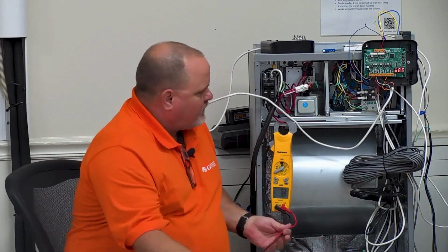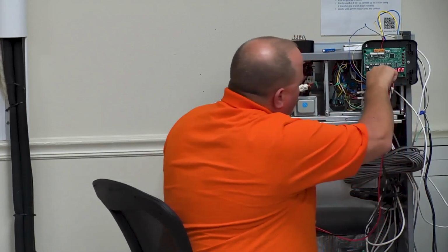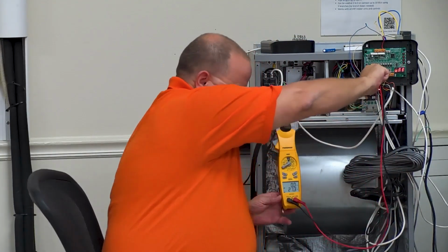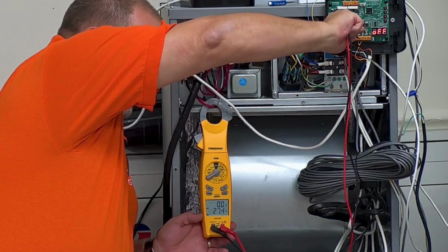So I got the voltmeter going on here. Let me get on O and C. And I got 27 volts. Hopefully my arm's not in the way. A lot of guys get confused by that. What I mean by that is your reversing valve call does not cycle with each call for operation. Your reversing valve is energized off of the system switch. So when you put the unit to heat mode, not emergency heat, put it to heat mode, that reversing valve is energized. It stays energized whether the machine's actually running the heat pump heating mode or not. Even when it goes into defrost, it doesn't change what your thermostat is doing. It is just disengaging the reversing valve on the outdoor unit to run in cool mode, turn off the outdoor fans, and run in defrost.